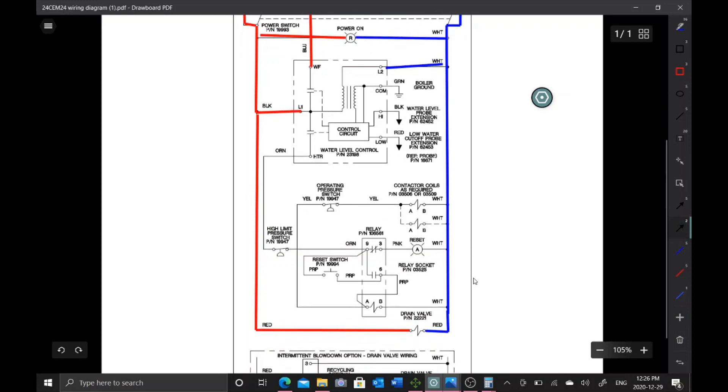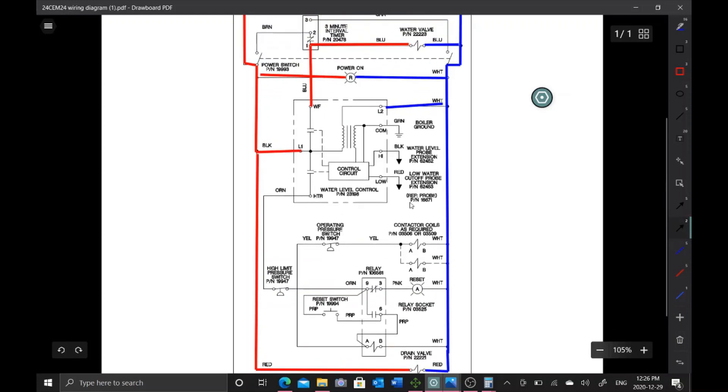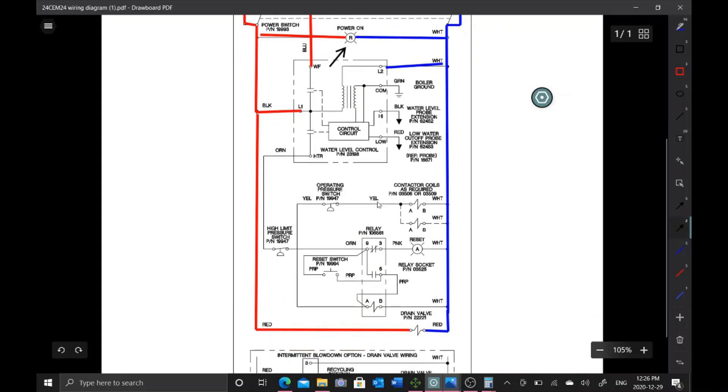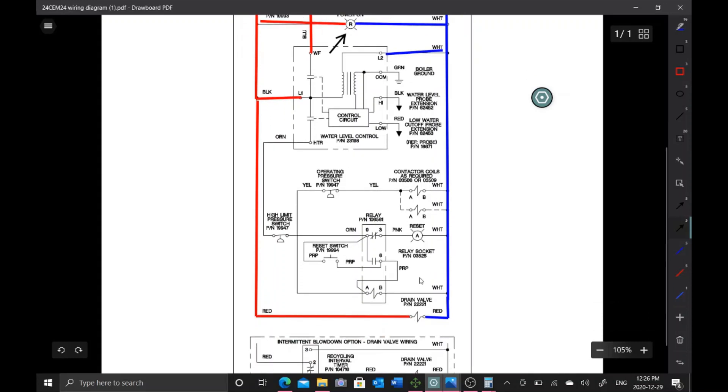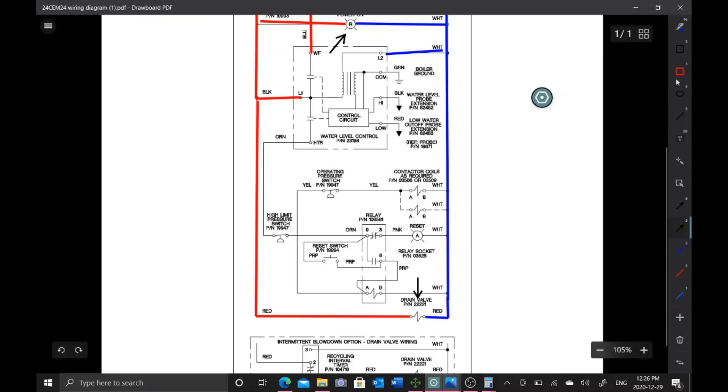First thing I did was reconnect the power light. The fuse did not blow. Then I reconnected this drain valve. The fuse blew, so this drain valve here is the issue.